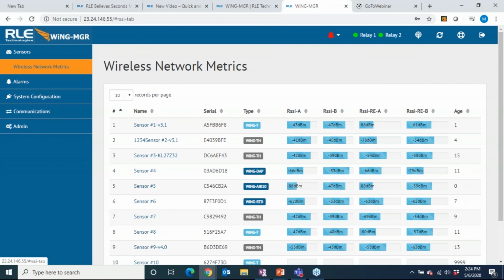When deploying wireless, the biggest challenge is often how good your wireless network is. So we built these response signals into the user interface, so we know at any time how good a signal our transmitters are communicating. As a general rule of thumb with radio frequency, you want to get as close to 30 as a good signal. When you start weaning out to 80 or 90, you want to figure out how to either move the transmitter antennas or potentially consider a range extender in some environments.